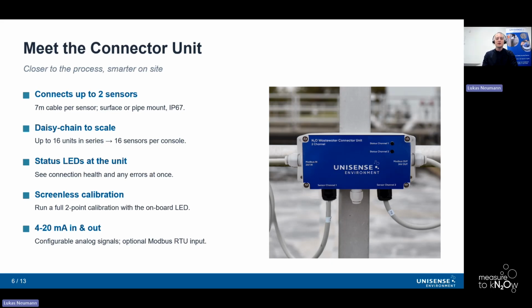Here at the connector unit, we also have the 4 to 20 milliamp in and out, where you can supply the airflow data input and dissolved oxygen input, and then we have the analog outputs to your SCADA for each respective sensor. Additional Modbus RTU for dissolved sensors is also available. A key point here is that the connector unit pushes the interface to where the work happens, at the sensor, at the tank, and not at the console.